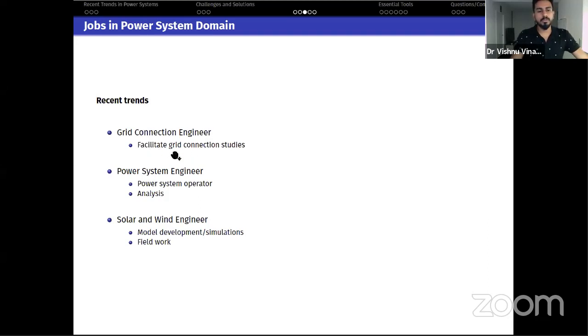The main responsibility is to facilitate grid connection studies. For example, if I constructed a solar farm in Cochin and wanted to connect it to the power network in India, I need approval from the relevant authorities. They will approve only if I can show that my system is stable, reliable, and won't cause trouble in the network. So when I construct a 100 megawatt solar farm, I need to show it will work fine and not impact other system components.